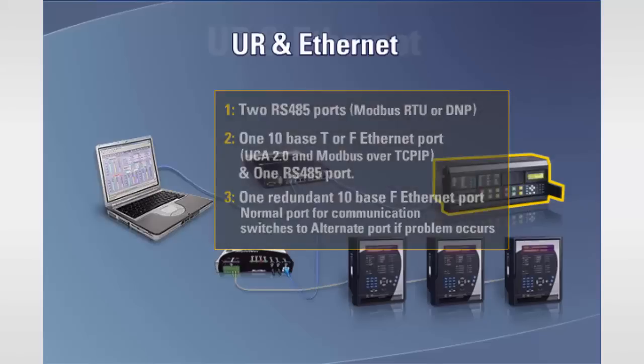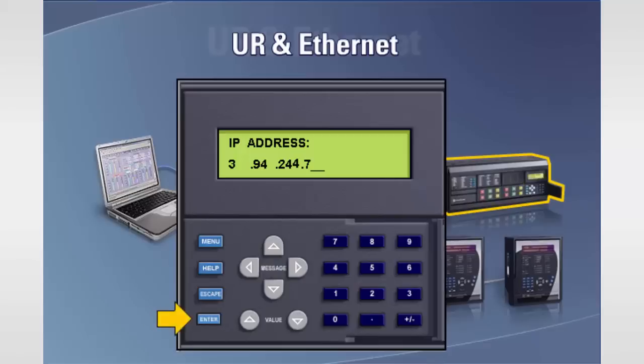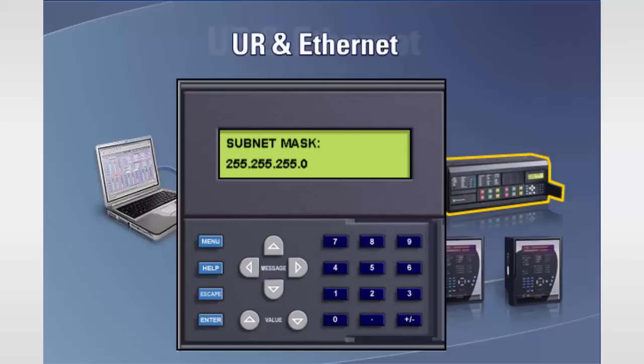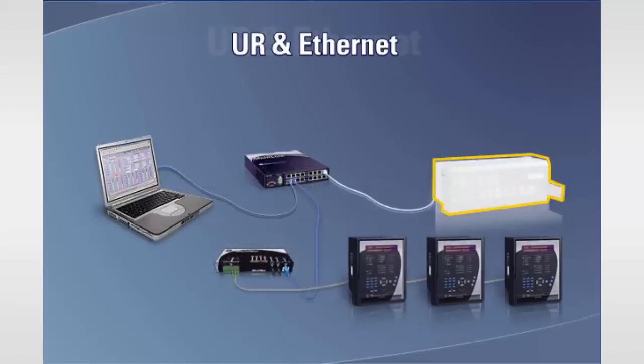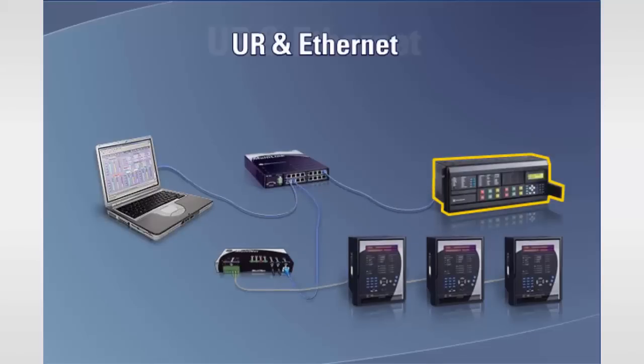Now we'll configure the UR. Using the keypad, enter a unique IP address and subnet mask. If using our test network addresses, the unique IP address will be in the range of 3.94.244.001 through 3.94.244.254 and the subnet mask will be 255.255.255.0. Set the Modbus address and configure the Ethernet port for full duplex. Connect the UR to the switch via a 10BASE-T cable and ensure that all appropriate sync lights are lit.